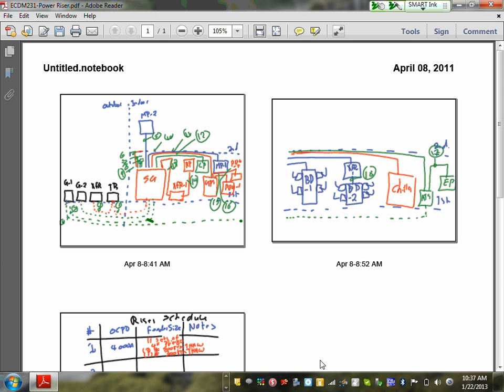With a normal data center where you have a PDU or something where you're transforming from 480 down to 208 or whatever, you only have to bring three phases in and then the transformer derives a neutral in the secondary. So this could all be three wire stuff up here. When you do that, the ground fault system is pretty easy because there's no neutral path.